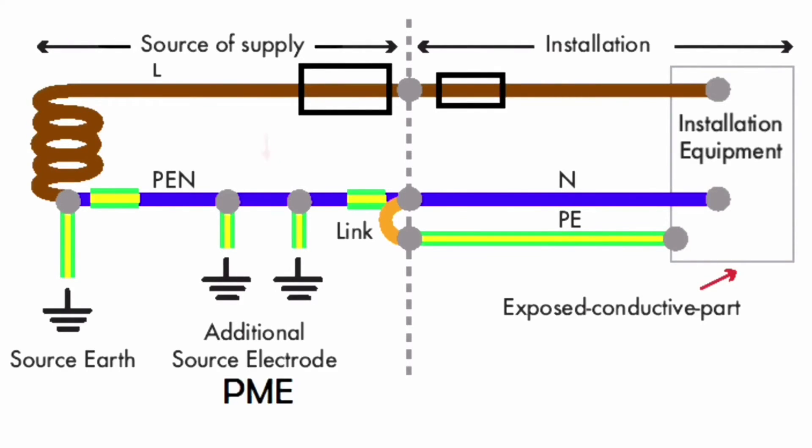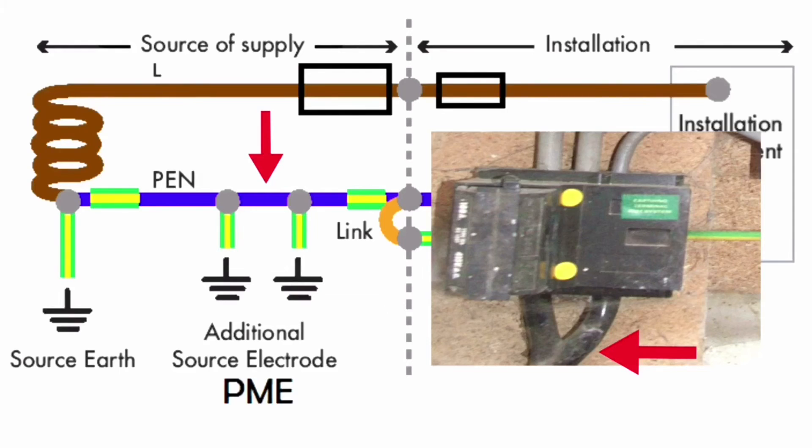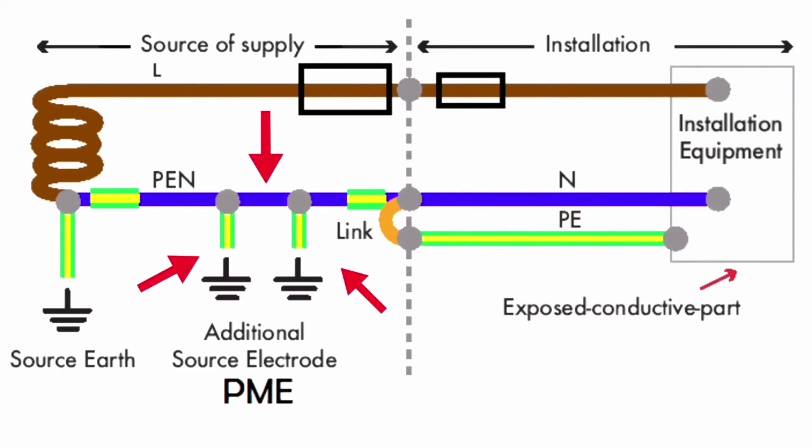This PEN conductor on the Supply Authority's side is staked throughout its run. We call this PME, Protective Multiple Earthing. This PME in the PEN conductor is very important, as loss of the Neutral on the Supply Authority's side would mean loss of the Protective Conductor in the installation. PME helps to prevent this happening.